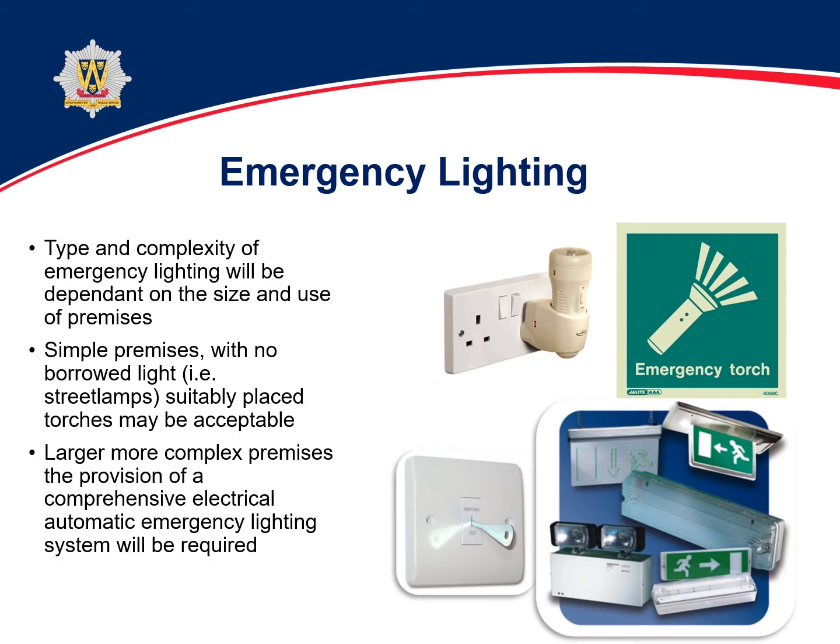Okay, emergency lighting then. Again, dependent on the size of your premises, your fire risk assessment should identify the level of emergency lighting required. As a simple rule, turn the lights off in the dark, see if you can find your way out easily. If not, then you need some form of emergency lighting. So small premises, torches could be used. Large, more complex, then fixed emergency lighting would be required.